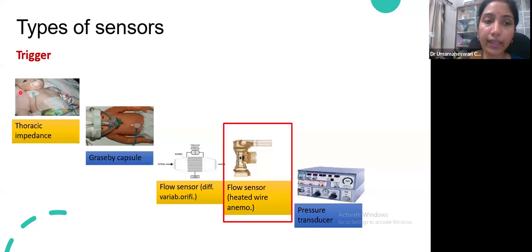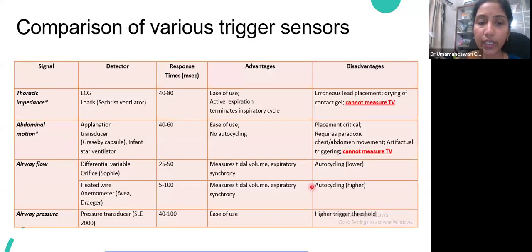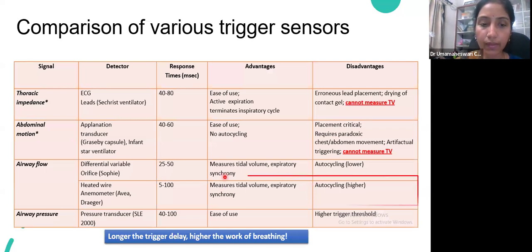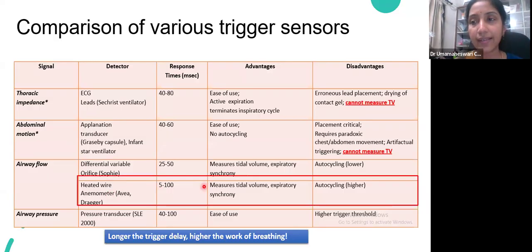The triggering can be by thoracic impedance, which is something like what the ECG picks up for the respiratory rate, very similar to that. It can be a special Graseby capsule, which all the apnea monitors use. Or it can be a specialized flow sensor, either a variable orifice flow sensor or a hot wire anemometer, or sometimes a pressure transducer. But majority of the time, we use a hot wire anemometer. It senses the difference in temperature when the baby is trying to breathe. That temperature difference is sensed, and it recognizes that the baby is going in for the inspiratory phase and starts the breathing.